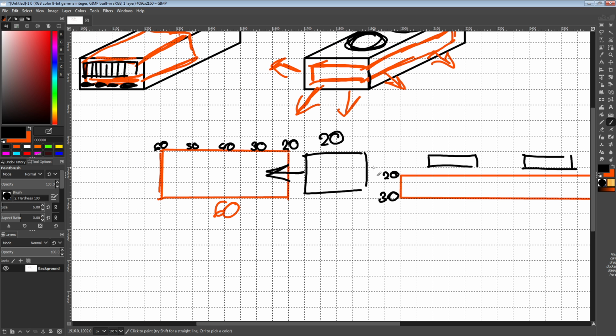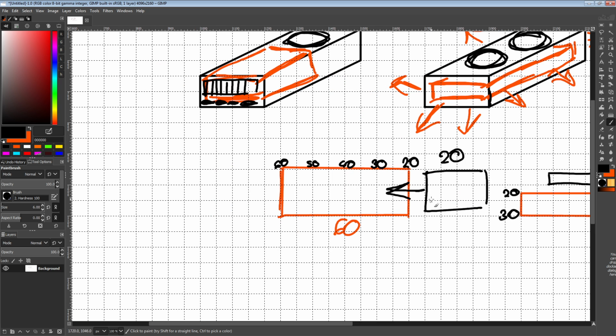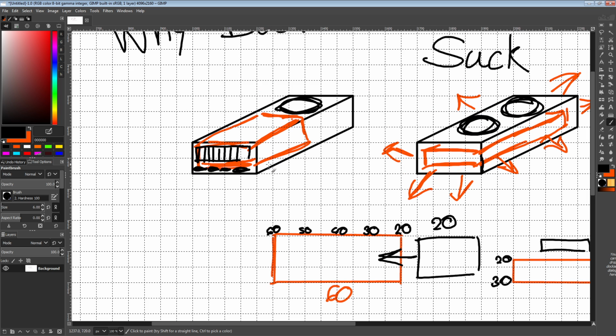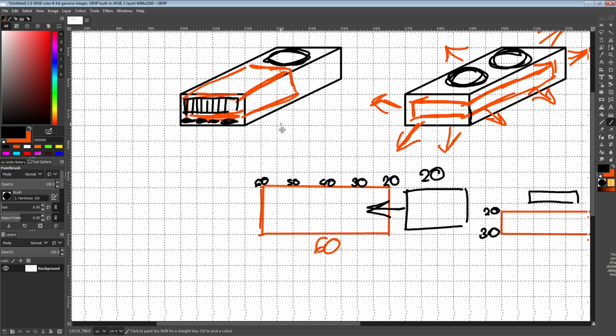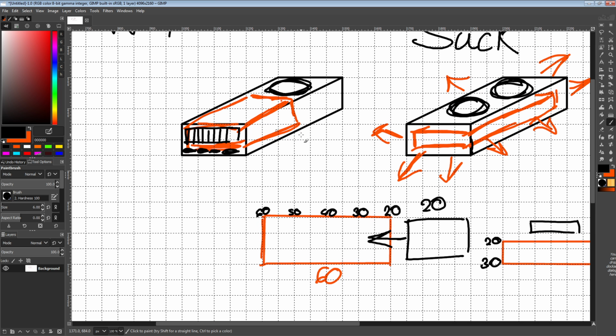And so, yeah, blower heat sinks. The funny thing about this situation with the blower heat sink fin stack is this is literally the worst way you could try to cool an object shaped like this. Because choosing to blow air through the card this way maximizes the depth of the heat exchanger and minimizes the cross-section.